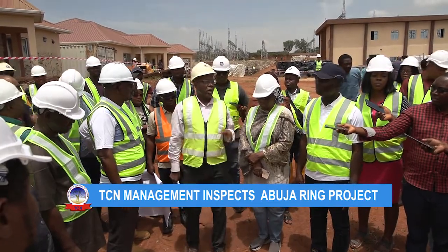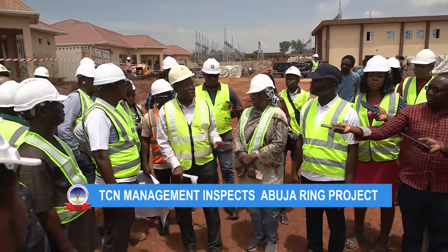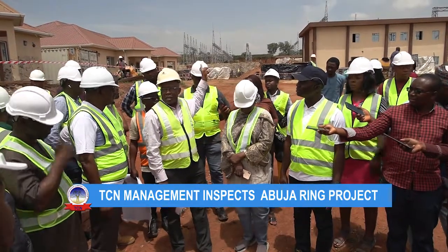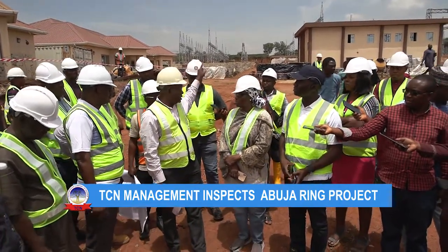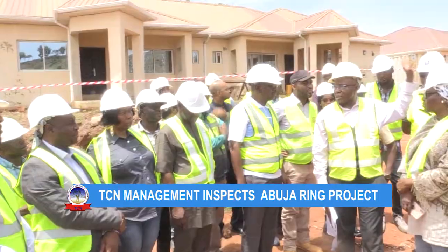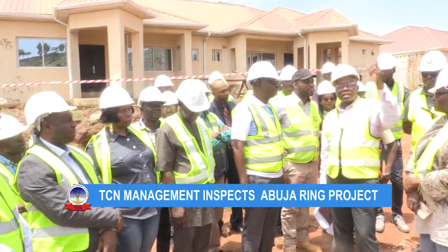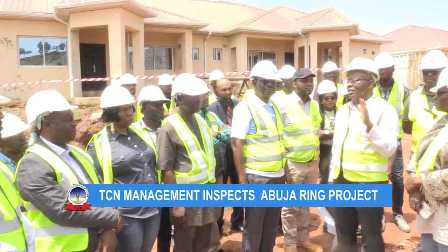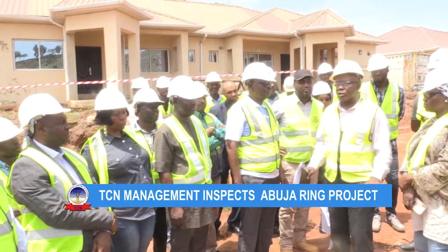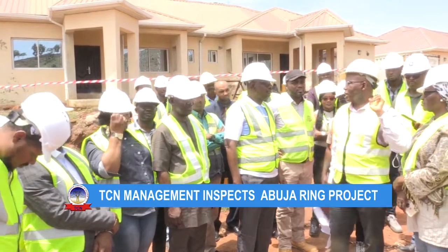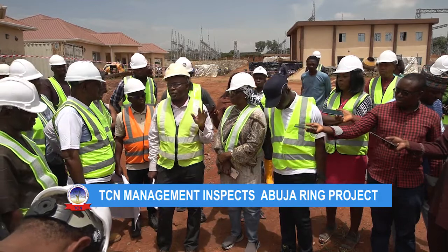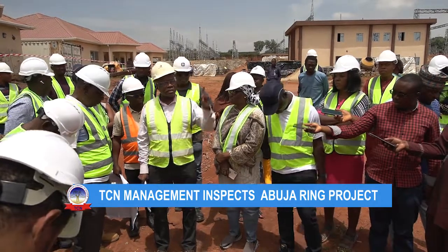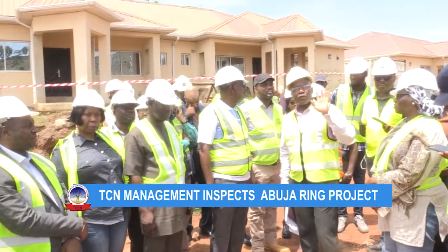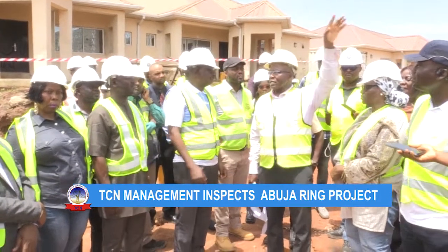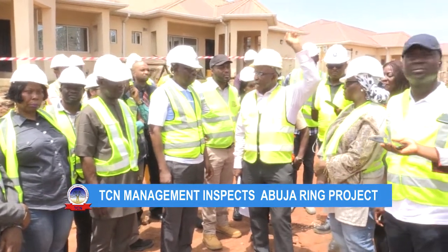Now, this project has a 2-bay extension in Old Apo that is nearing completion too. Then there is the second 330 kV line coming into FCT, coming to this substation. The third 330 kV transmission line coming into FCT comes through here, and for that we have a bay extension at Lafia.